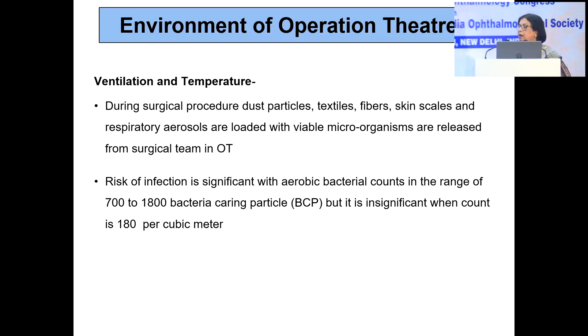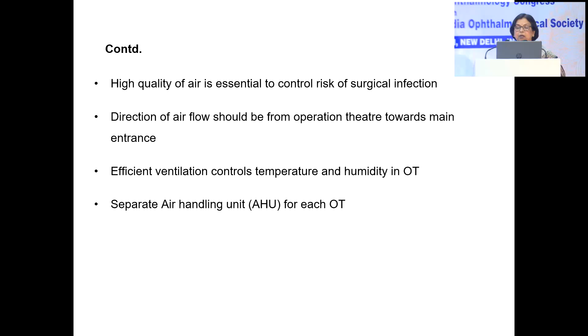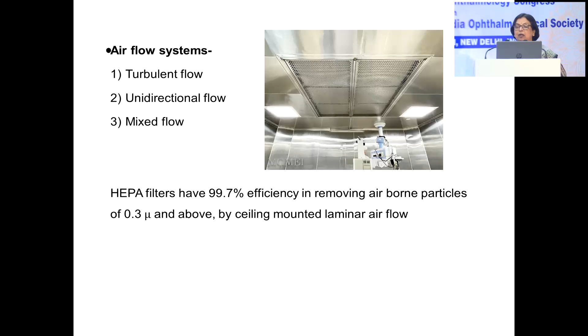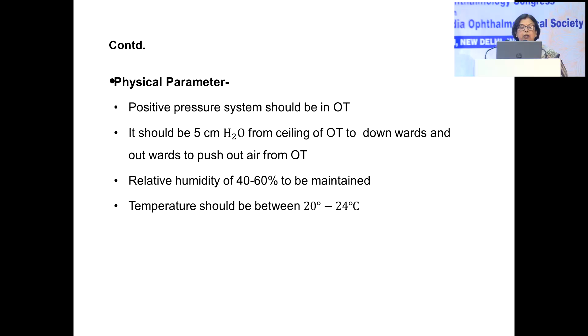The direction of flow should be from the operation theatre to the main entrance. Efficient ventilation controls temperature and humidity in the operation theatre, and a separate air handling unit should be provided for each theatre. The air flow should be unidirectional. HEPA filters have 99.7% efficiency in removing airborne particles of 0.3 micron and above, with ceiling mounted laminar air flow. As physical parameters, a positive pressure system should be in the operation theatre, 5 centimeters H2O, from the ceiling of the OT downwards and outwards to push the air out of the OT. Relative humidity should be 40 to 60% and temperature should be 20 to 24 degrees centigrade.